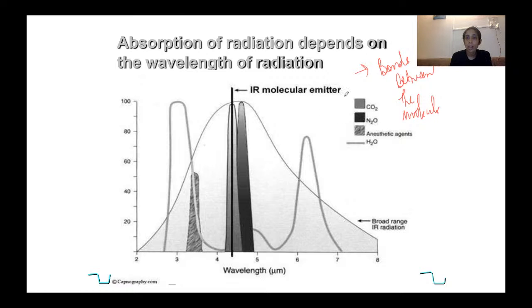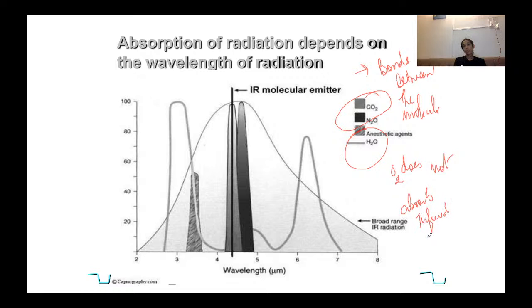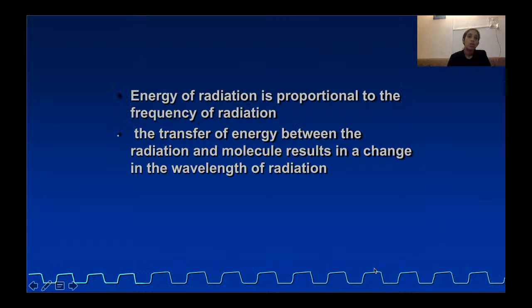Okay, so basically your carbon dioxide, nitrous oxide and anesthetic agents are the ones which absorb infrared radiation. Your oxygen does not absorb infrared radiation. So you cannot monitor oxygen with this infrared radiation. Carbon dioxide, nitrous oxide and inhalation agents are monitored. So energy of radiation is proportional to the frequency of radiation, and the transfer of energy between the radiation and the molecule results in a change in wavelength of the radiation.